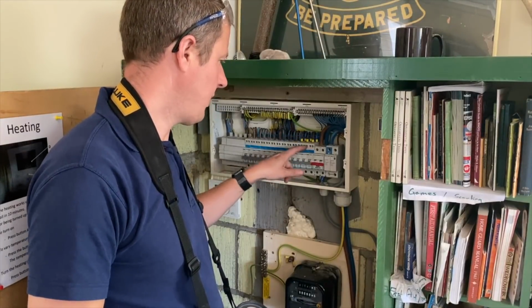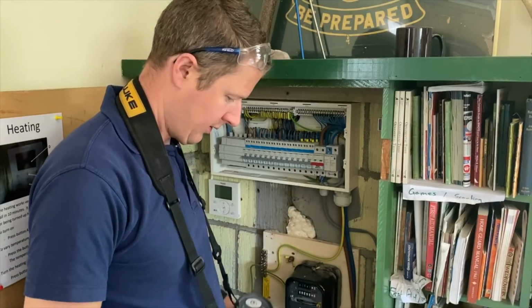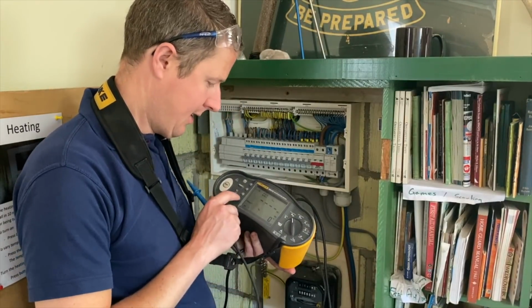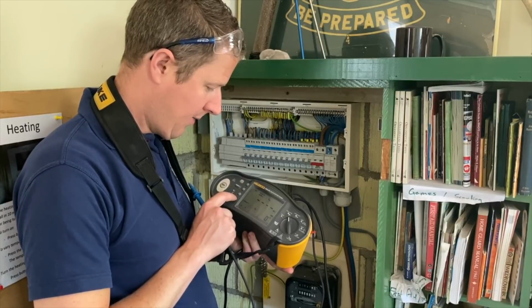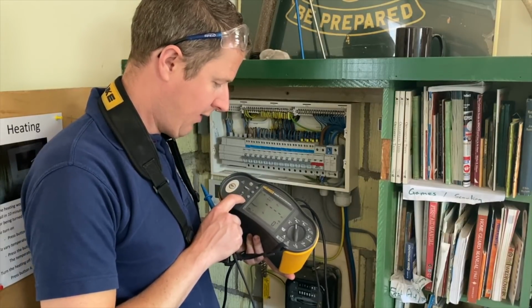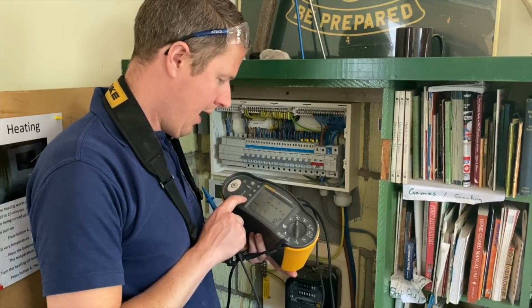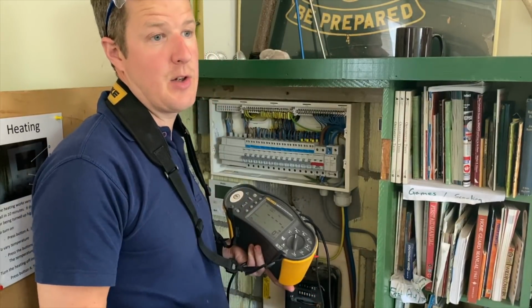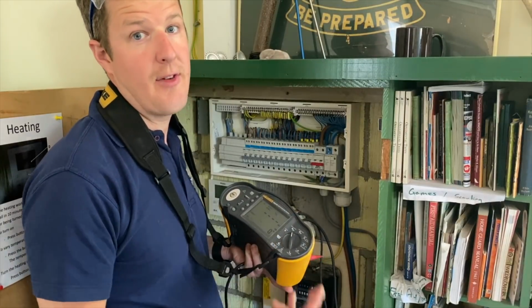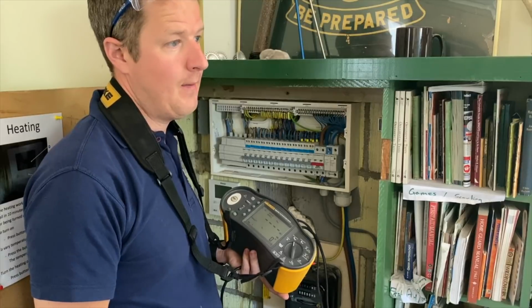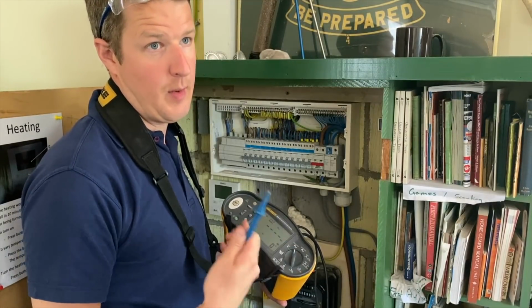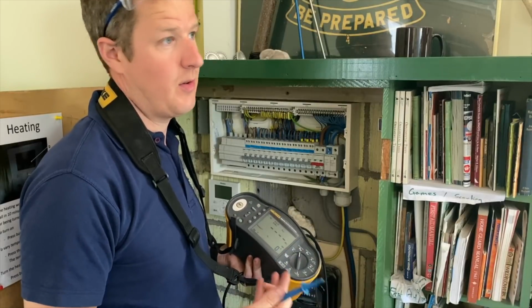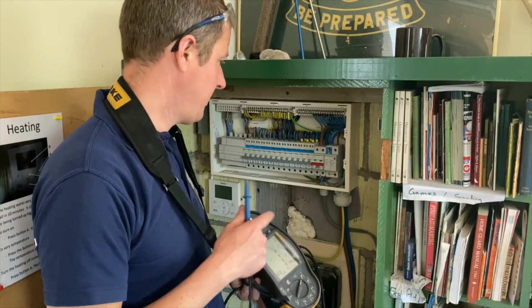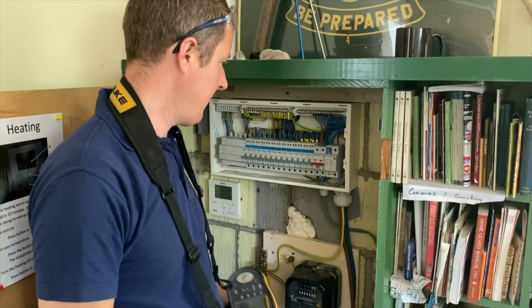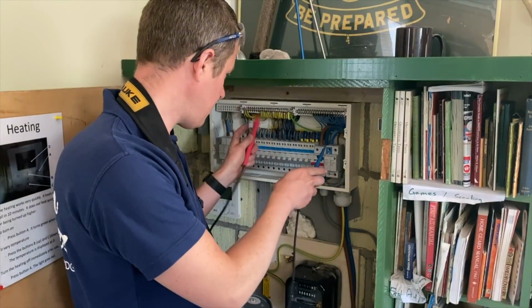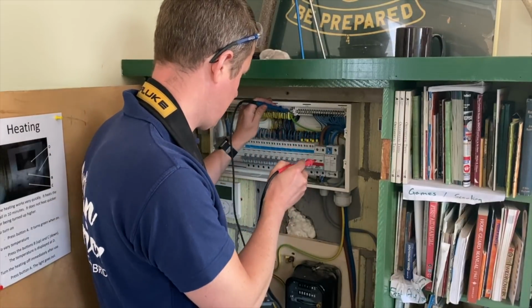So we'll start with circuit number 1 and we'll just work our way across. Now the tester has several voltage settings for insulation resistance. It goes up from 50 volts to 100 volts, 250 volts, 500 volts and 1000 volts. Now it's recommended to test an installation that will normally run at 230 volts at 500 volts. However, if there's a risk of damaging sensitive equipment, then we can rather just test at 250 volts to make sure that there's no risk there. I will test at 500 volts between phase to earth and neutral to earth and see what we get. So we'll start with circuit 1, which is the air conditioning units.